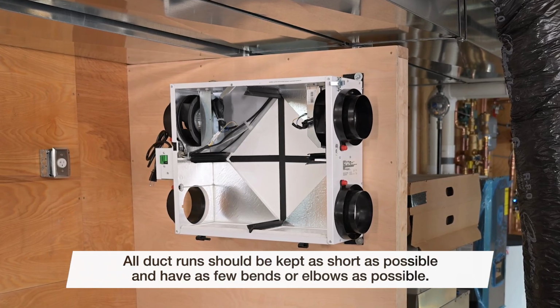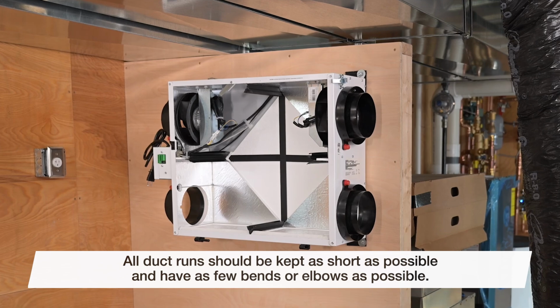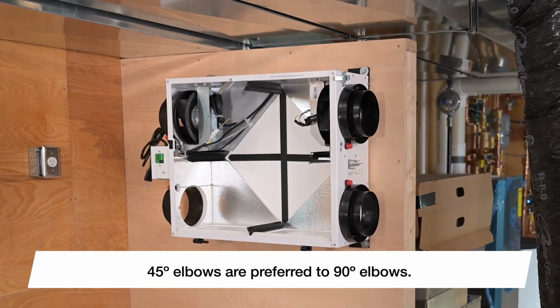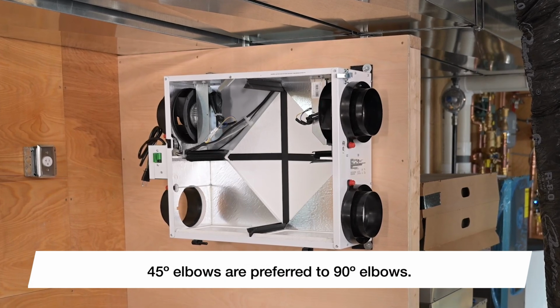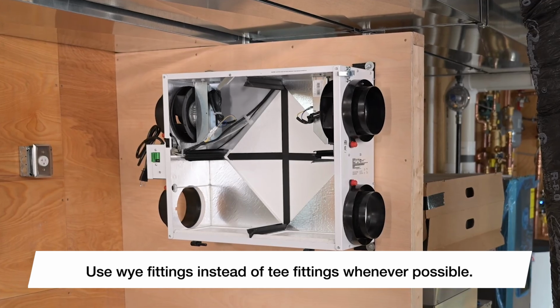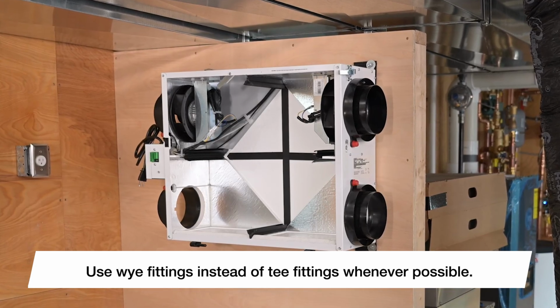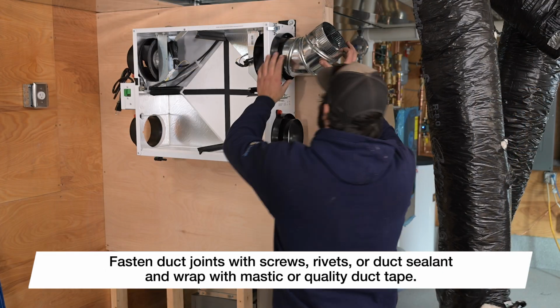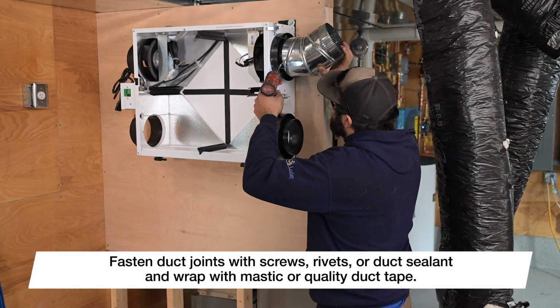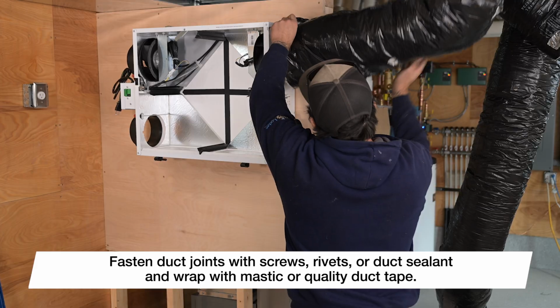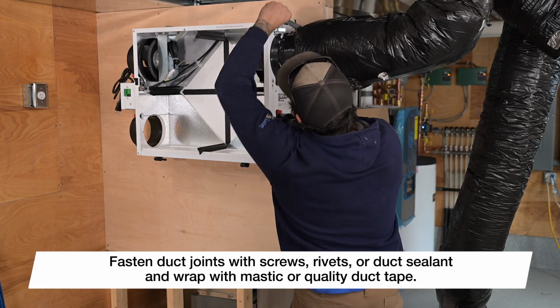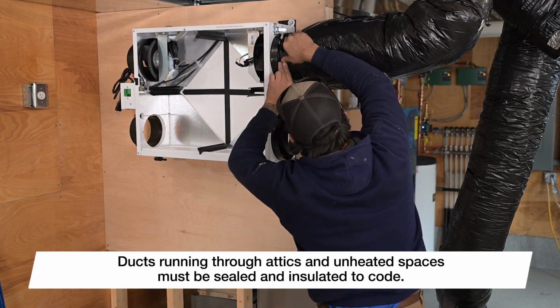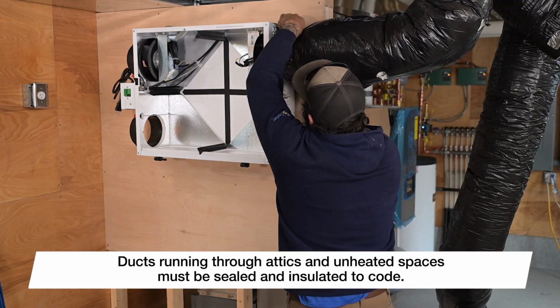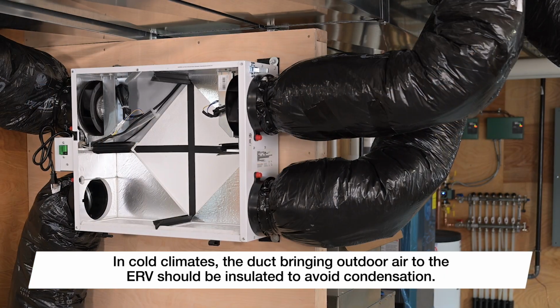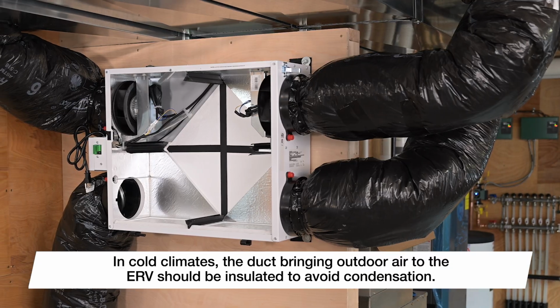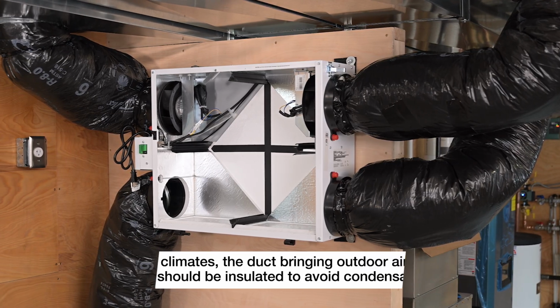All duct runs should be kept as short as possible and have as few bends or elbows as possible. 45-degree elbows are preferred to 90-degree elbows. And use Y fittings instead of T fittings whenever possible. All duct joints should be fastened with screws, rivets, or duct sealant and wrapped with mastic or quality duct tape to prevent leakage. And all ducts running through attics and unheated spaces must be sealed and insulated to code. In cold climates, the duct bringing outdoor air to the ERV should be insulated to avoid condensation.